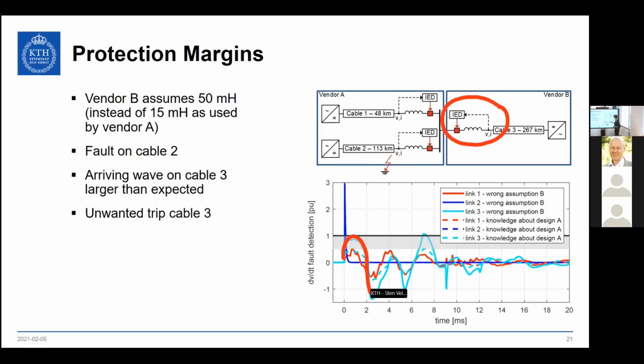You can see here how it goes above threshold just by a tiny bit, but that's enough to trip it. And if the new vendor B had known the correct line inductor size, it would have designed the fault detection in a different way such that it would have behaved as I indicate now. So here we would still have had a nice protection margin, and then with that knowledge, the link would not have been disconnected.